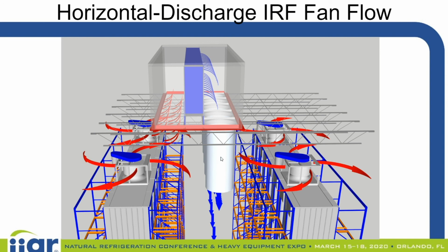So they historically have caused some defrost challenges with in-room evaporators. So there's typically not an operational challenge with penthouse evaporators that have a discharge duct that routes the air all the way down past that level.